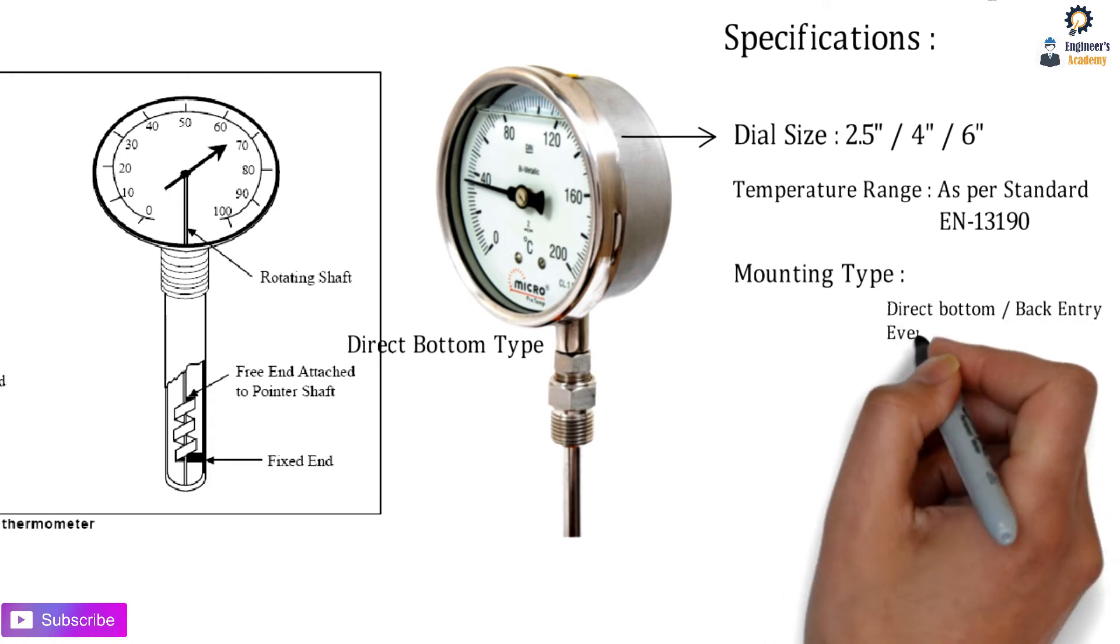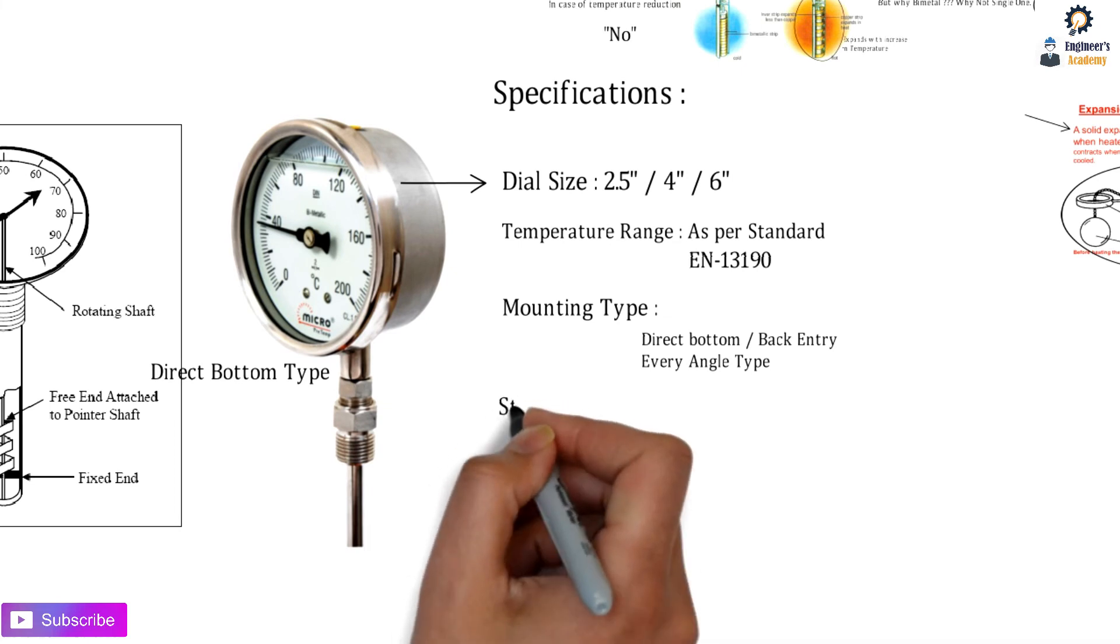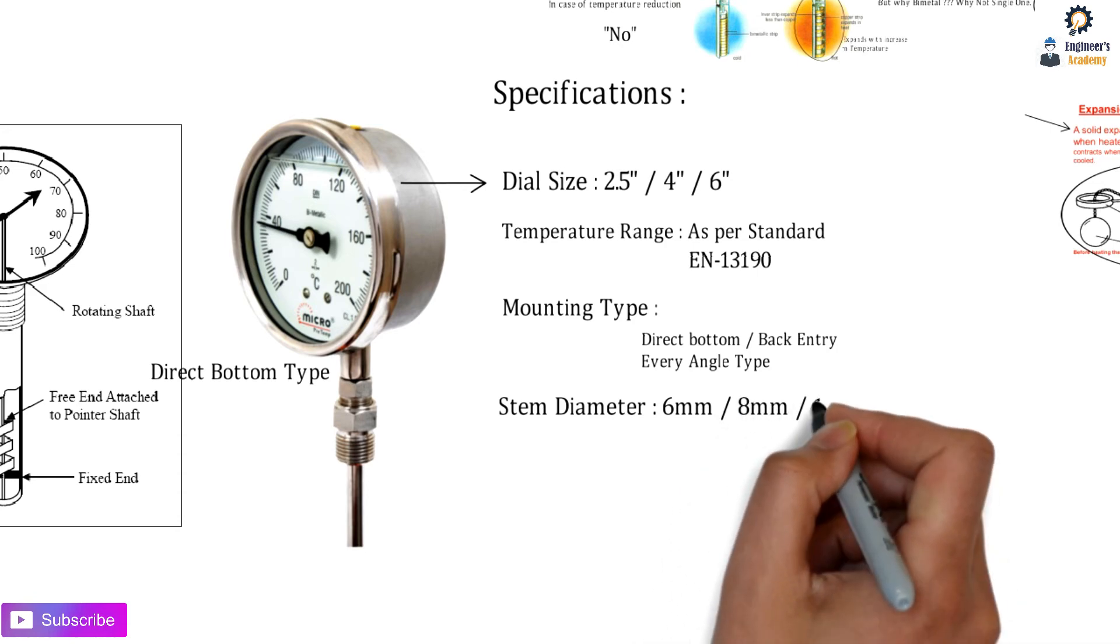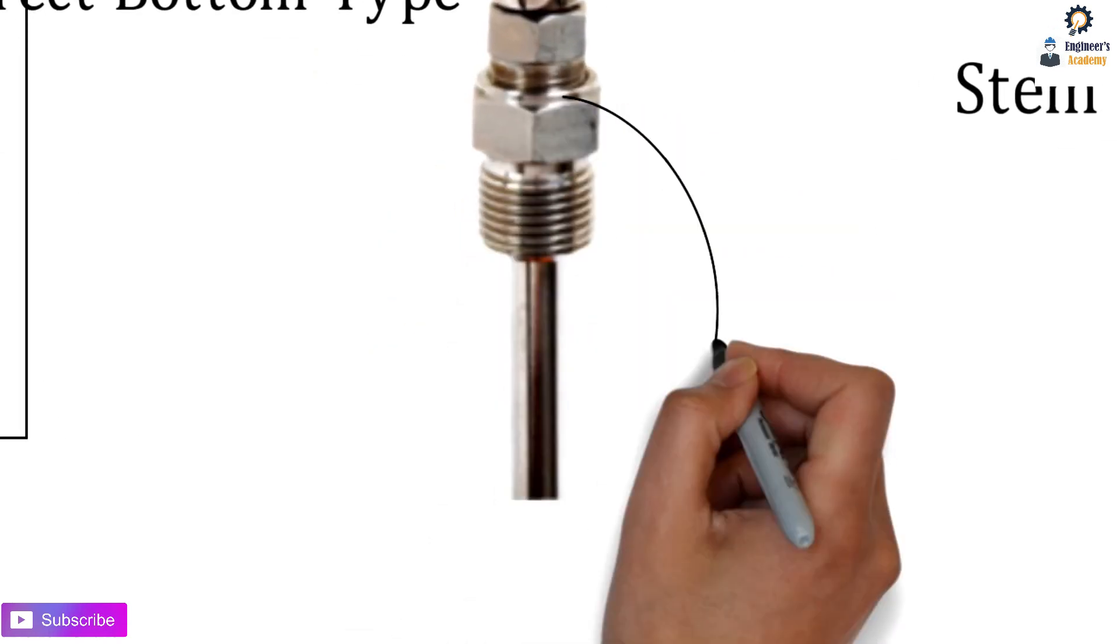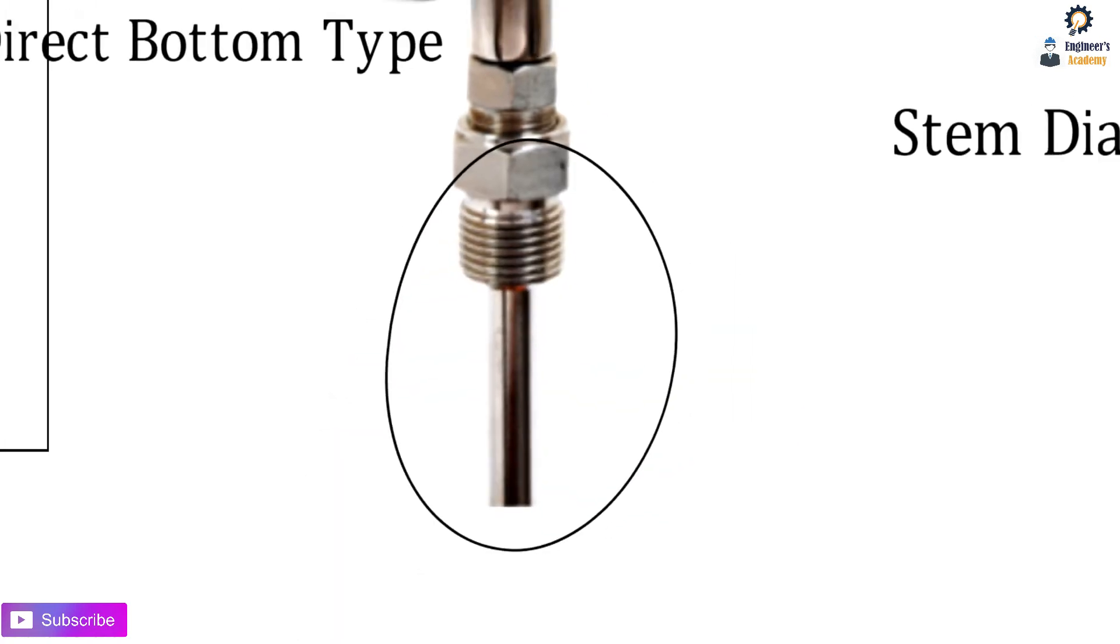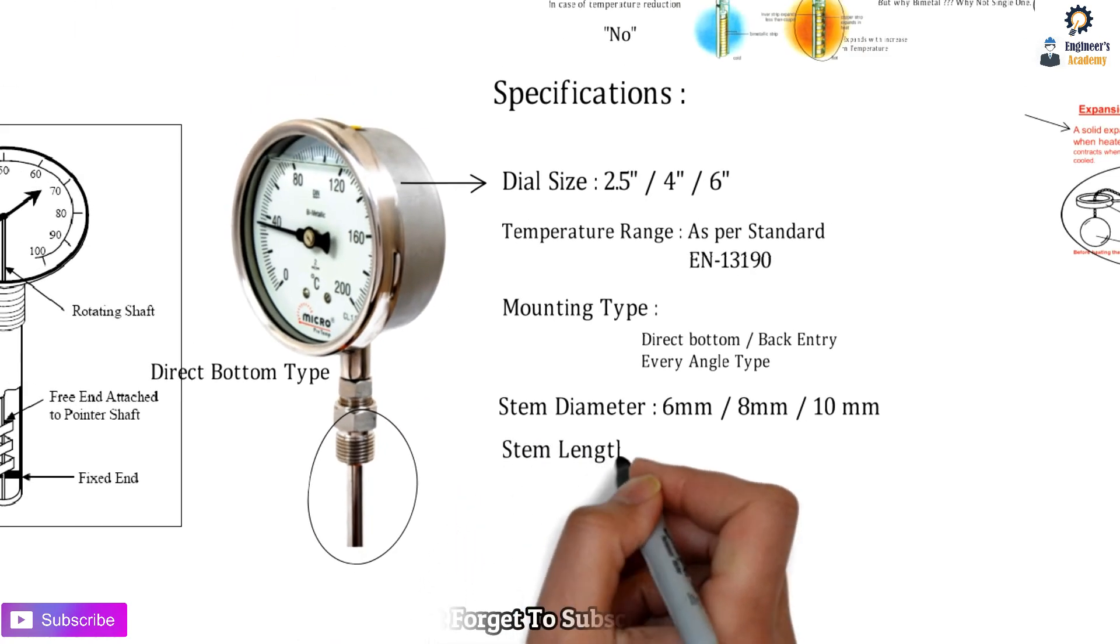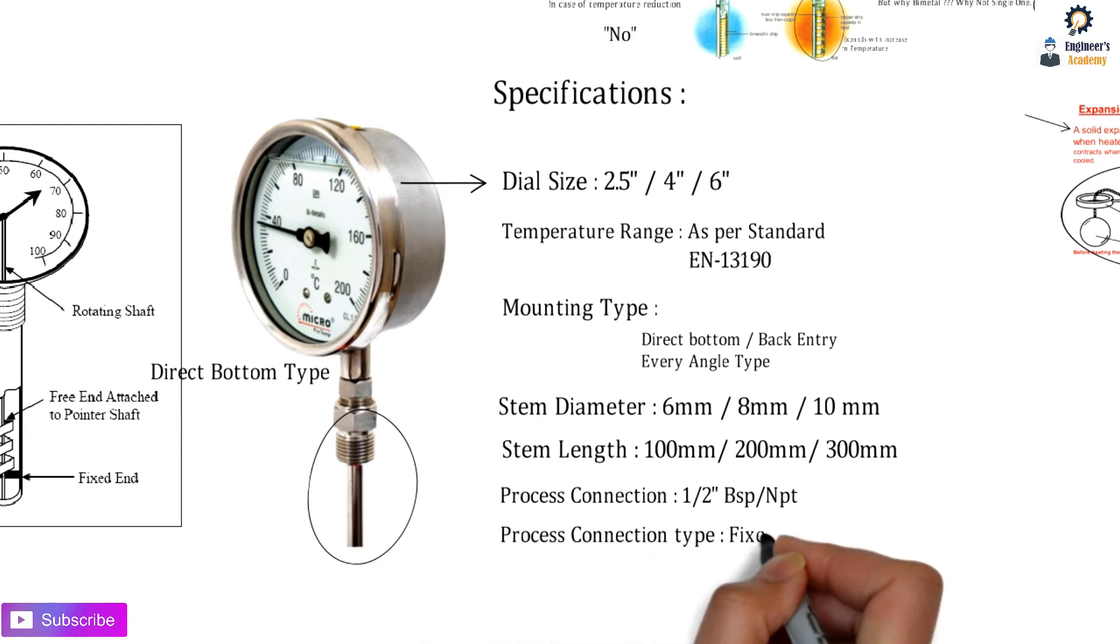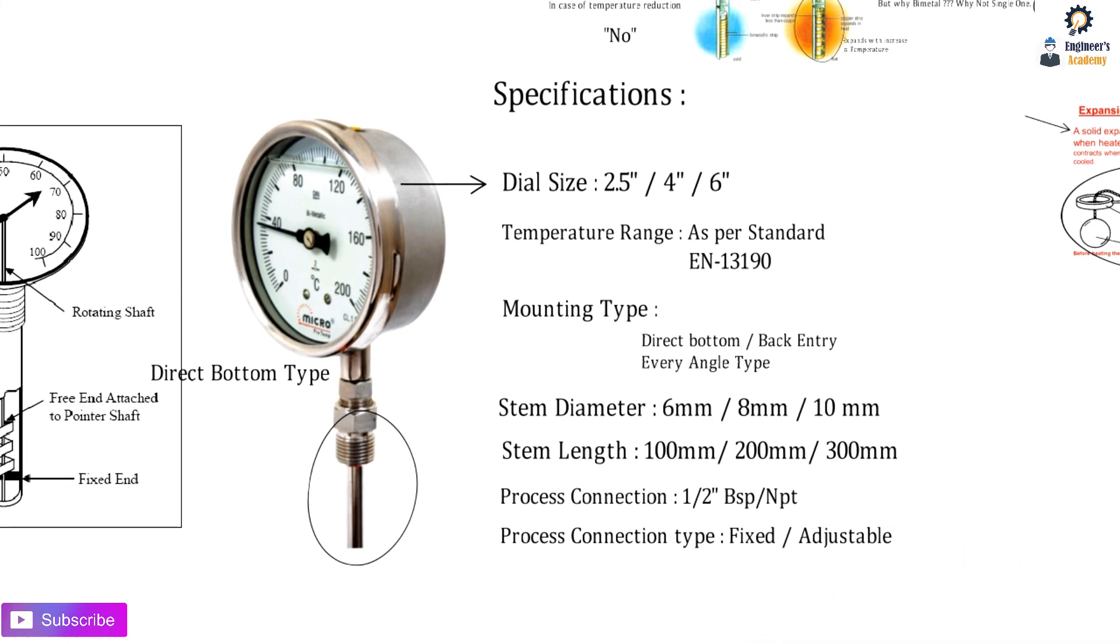Next is the stem diameter, which can vary from 6mm, 8mm, or 10mm. The stem length depends on customer requirement - 100mm, 200mm, or 300mm. The process connection determines how we fix this to the equipment - it can be half inch BSP or NPT, fixed or adjustable. These are all the specifications needed for a bimetallic temperature gauge.